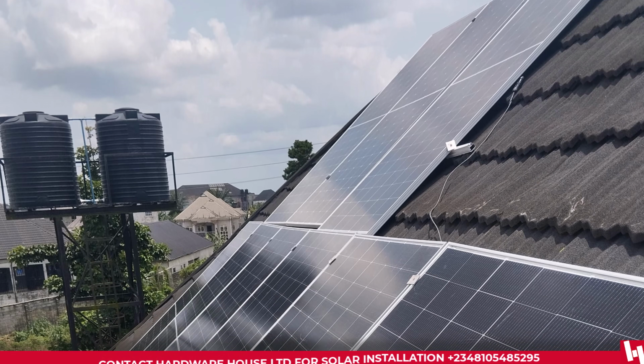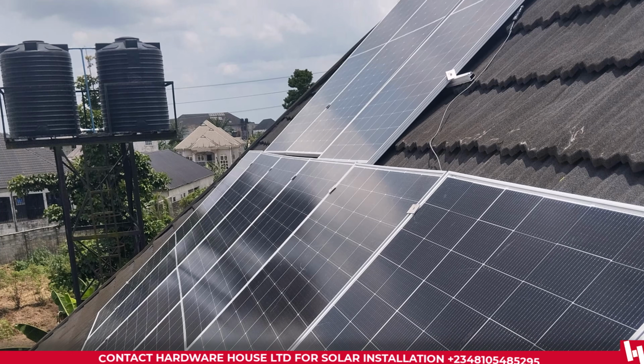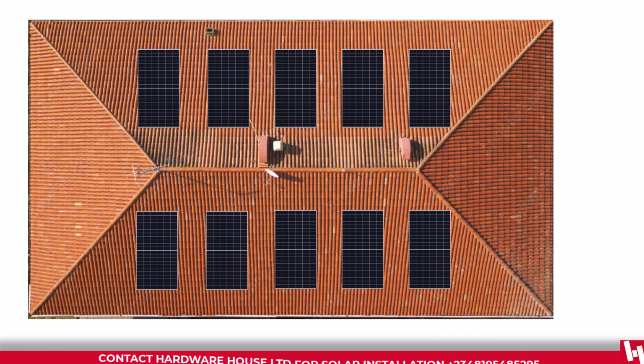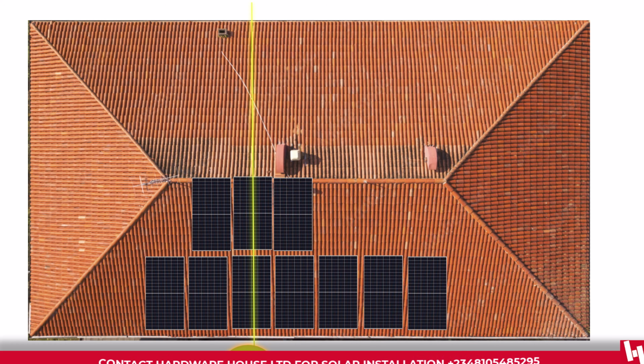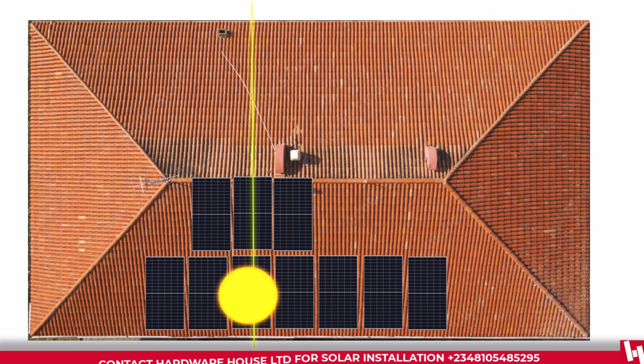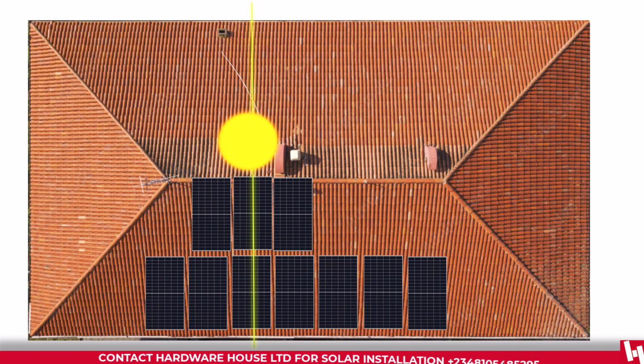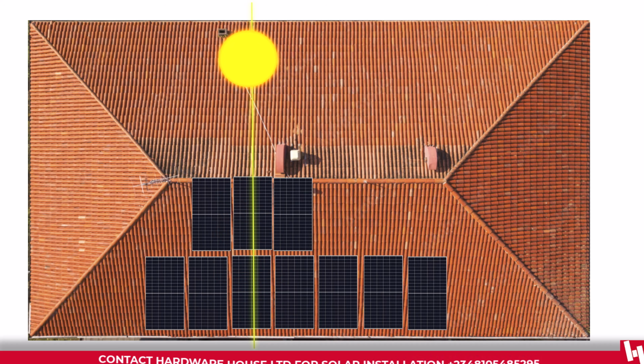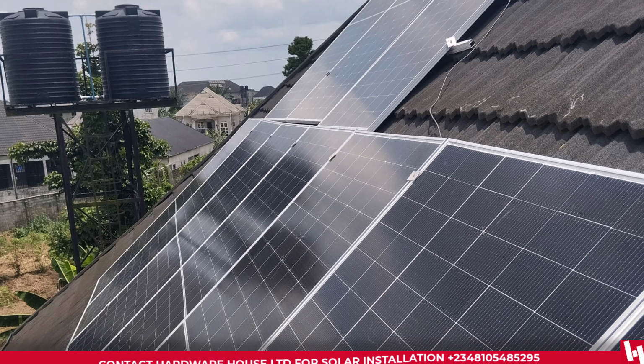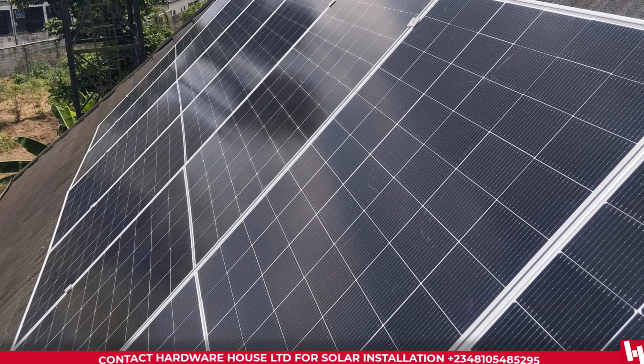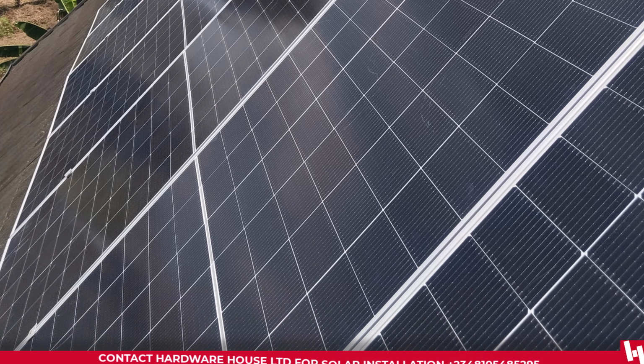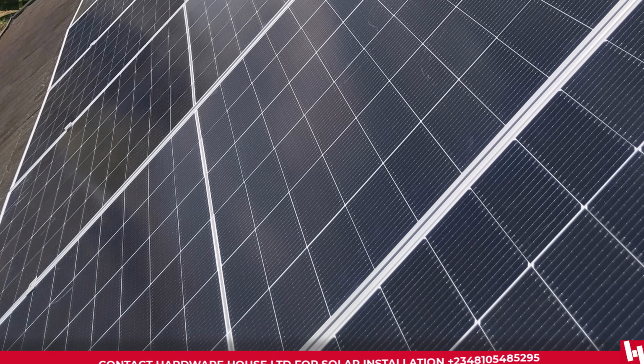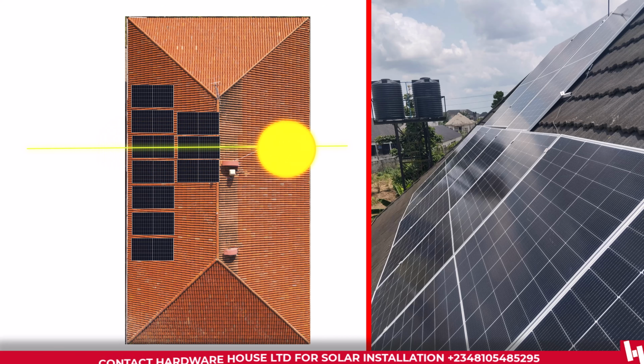So for the position on the roof, there are two ways we would have arranged the solar panels. The first would have been to split it into 5-5 facing different directions of the roof. But we traced the path where the sun rises from, and we were able to position all 10 solar panels to face that position where the sun rises from. That way you're able to get maximum power during the early morning period, and you're able to get a full charge on the battery early enough so the inverter can focus all the power from the solar panels on the house, because it's done charging the battery. The battery will only be helping. So all 10 panels were facing the same direction.